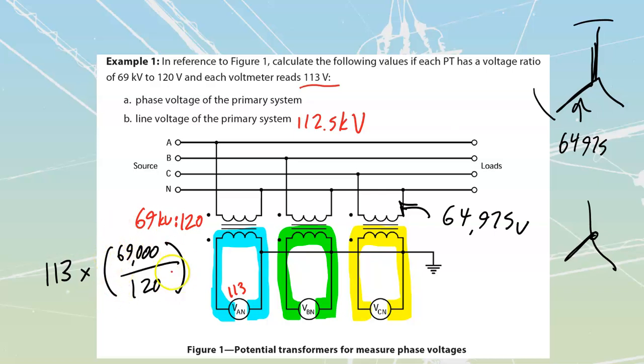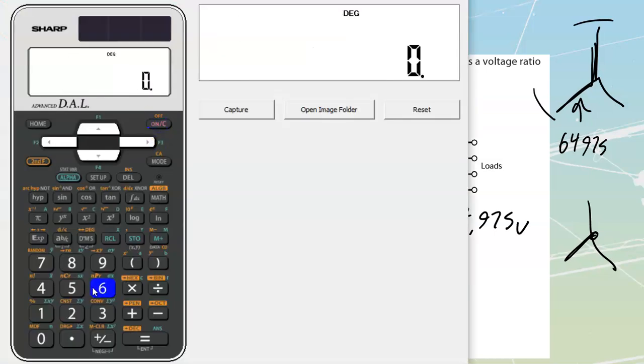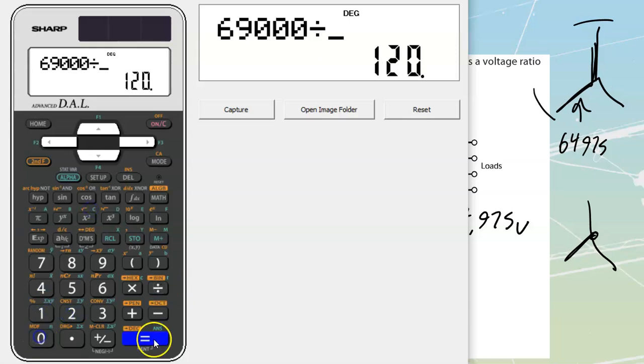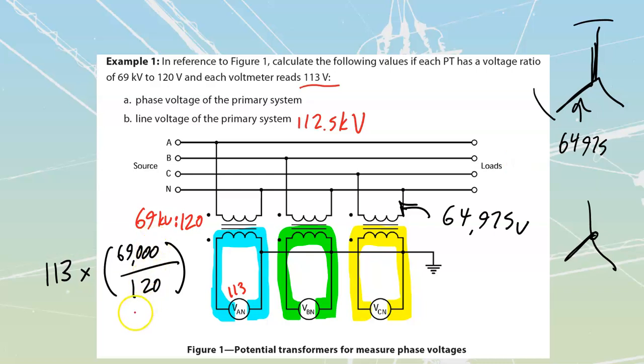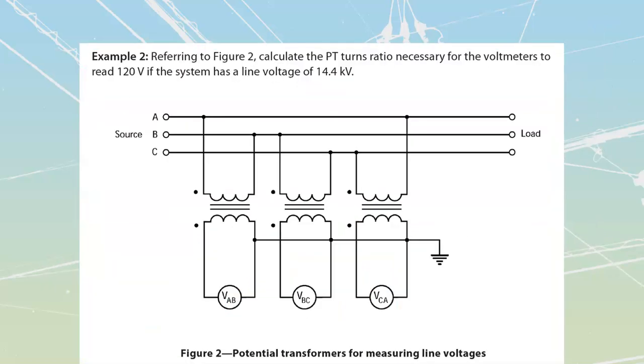Just remember, we're able to use this as a ratio like this. I could have also simplified it from 69,000 over 120. If you want, it's allowable. We'll just show that 69,000 divided by 120 means that the actual turns ratio is going to be 575 to 1. So I could have done this times 575 to 1, which we simplify to just 575 at that point. We could have used that inside there because that's what it's equivalent to. Okay, let's take a look at our next one over here.